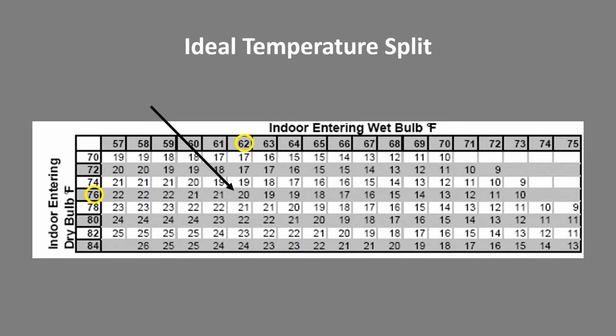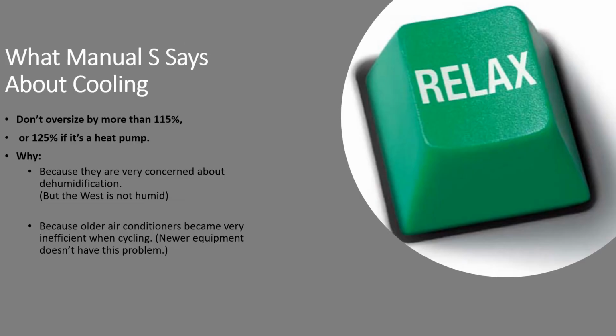But just to say you get out there, and it's early in the day, the system hasn't been running to dry out the air. It's a little muggy. Let's just say you got a 68-degree wet bulb, which is pretty wet, and a dry bulb of 78. Well, then your expected temperature drop across the coil will be 17. Let's say you had a 72 degrees indoor dry bulb temperature, then you'd only be expecting a temperature drop of 14. So while the 20 degrees generally works for us in the Northwest, it's still nice to know something about the psychrometric conditions you're testing under.